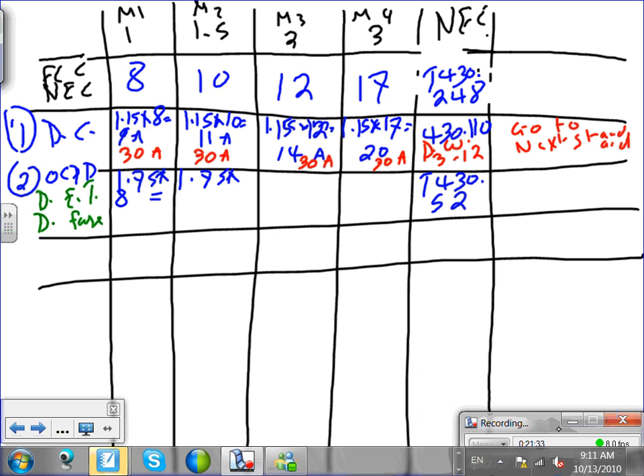1.75 times 8, and then also 1.75 times 10, 1.75 times 12, and 1.75 times 17. And to find the standard, after you get there, guys, you're also going to go to which table? 240.6. To find the standards for them, you need to go to table 240.6. Okay. Can anybody do the calculation for me? So 1.75 times 8 equals 14.